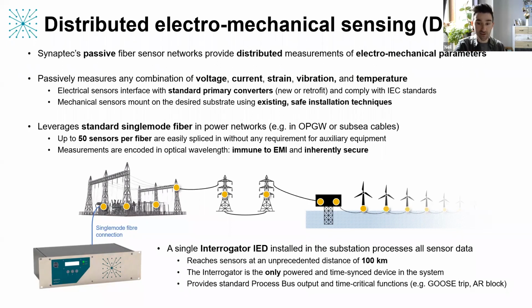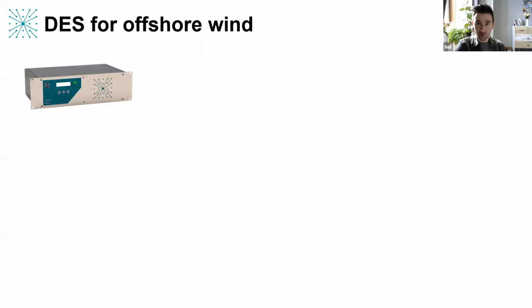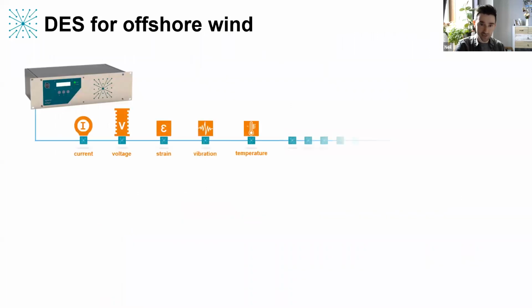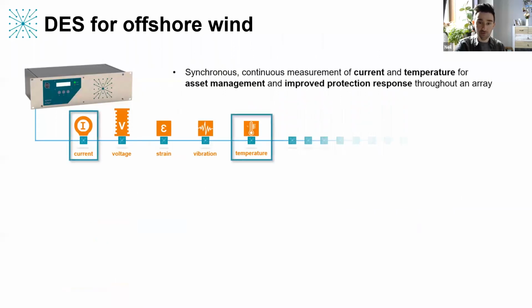In terms of outputs from this device, we would have standard measurement outputs to the process bus, so digital sampled values, and also measurements going to our own software system, which we'll talk about a bit later on, which will do more advanced analytics on the power quality and the condition monitoring side. So for offshore wind, we have this platform technology with the interrogator and all these different measurements that we can gather with that system. But for the offshore side, we're focusing first of all on synchronous and continuous measurement of current and temperature, in particular in the turbine transition piece. And that's to be used for improved O&M response to faults and for improved asset management throughout an array.